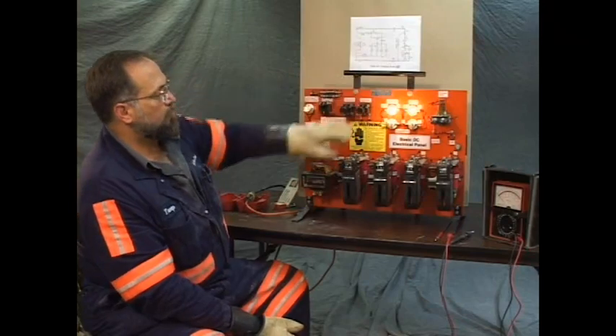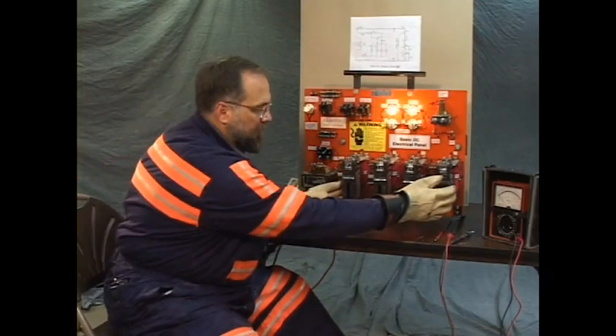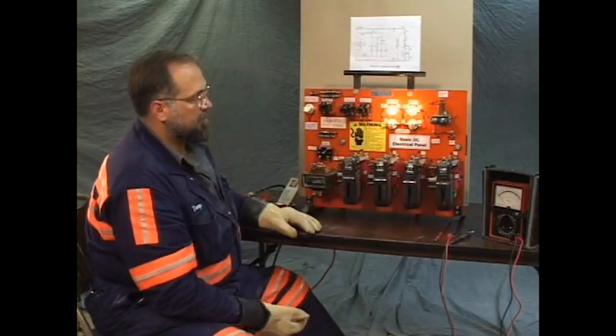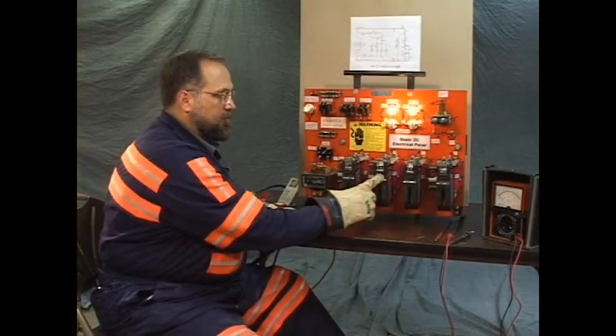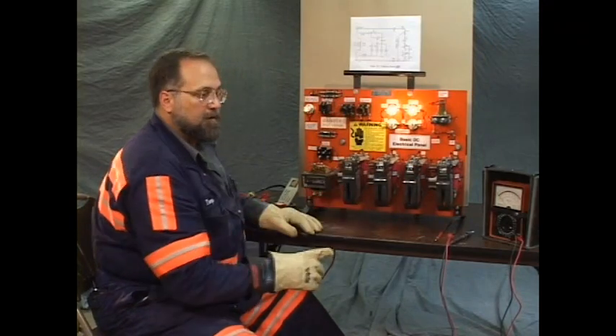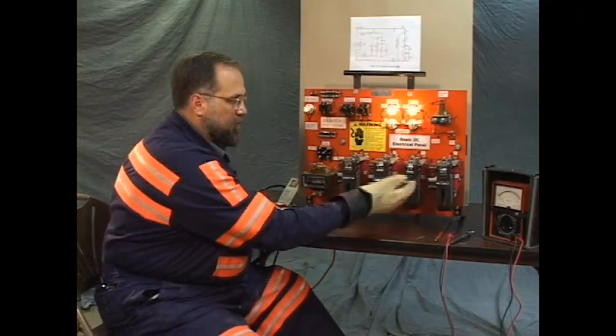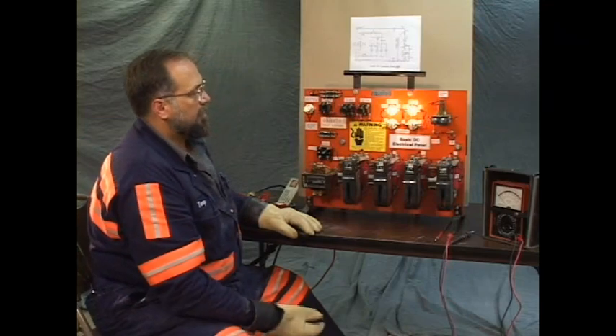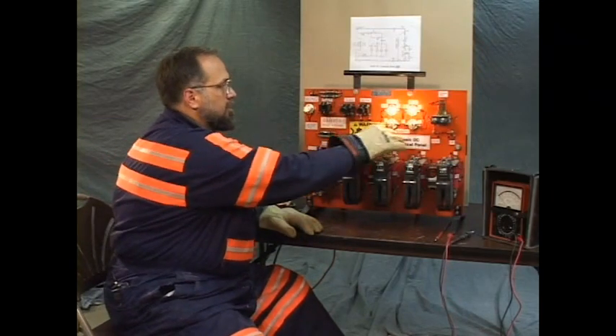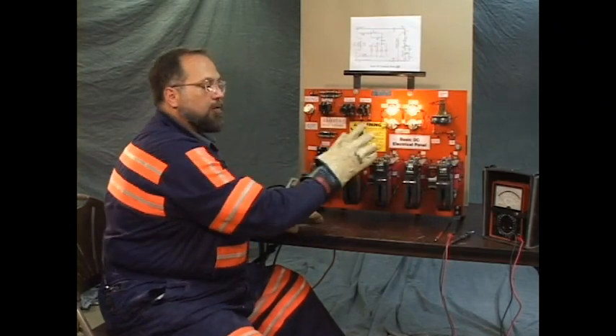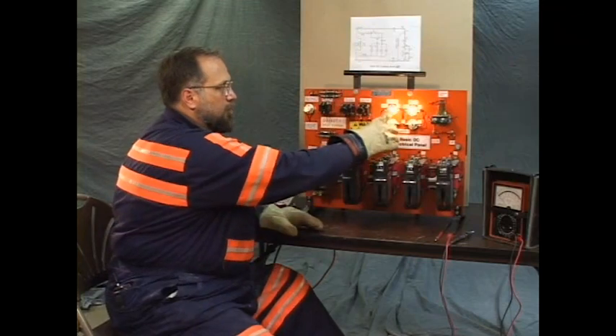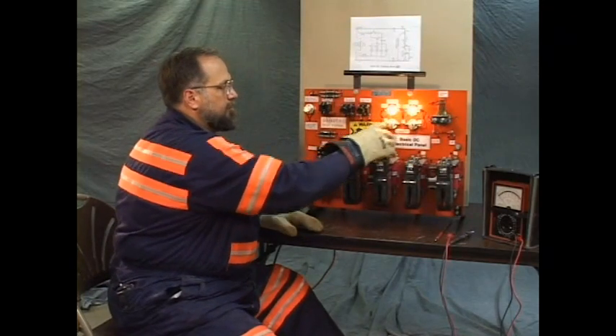And that's normal operation. M1 and M2 go in simultaneously. After 1 second, 1A closes. After 1 more second, 2A closes. The effect of that on the lights. They all 4 come on at first. This one bright, these 3 dim.